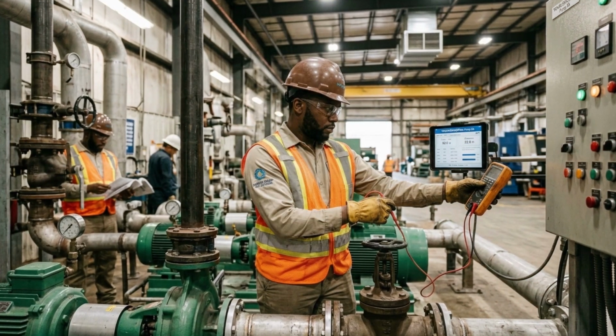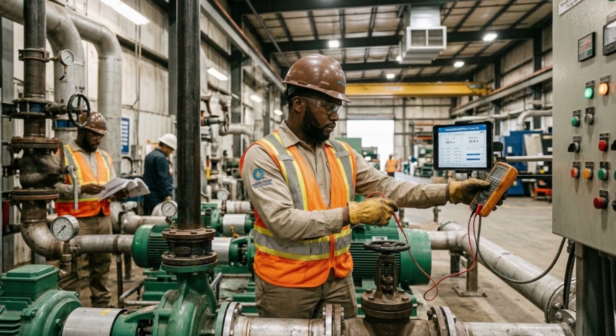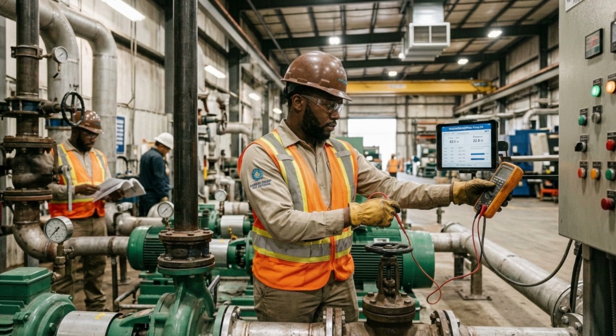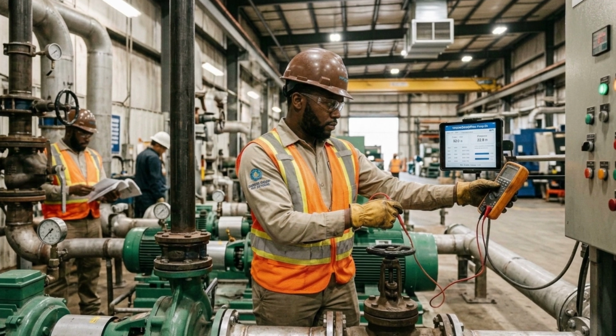3 in the morning, a pump station. The discharge pressure gauge is reading low. An alarm's been chattering for the last 20 minutes, and the operator on shift has already tried the one thing he knows how to try. He swapped the pump, pulled the duty pump offline, brought the standby online, hoping that whatever's wrong just goes away with the new machine. It doesn't go away, because the pump was never the problem.